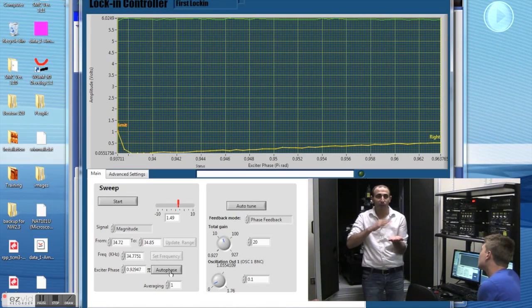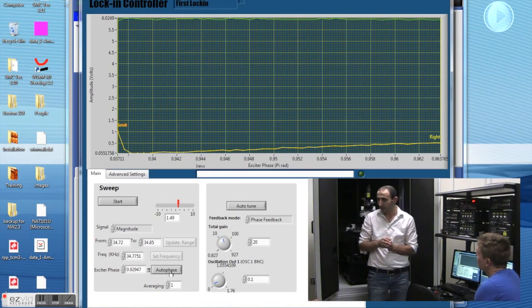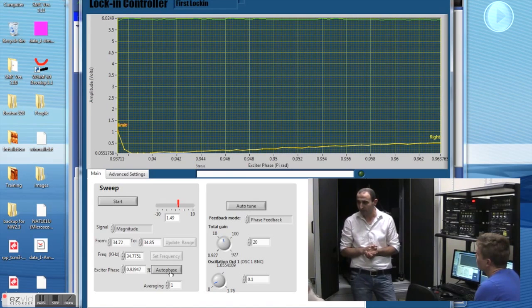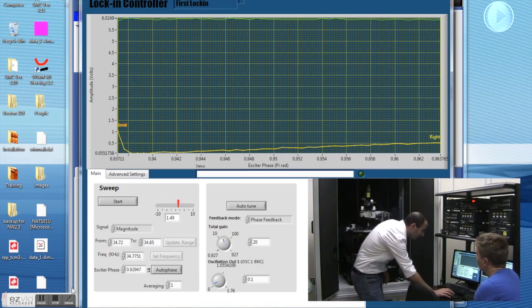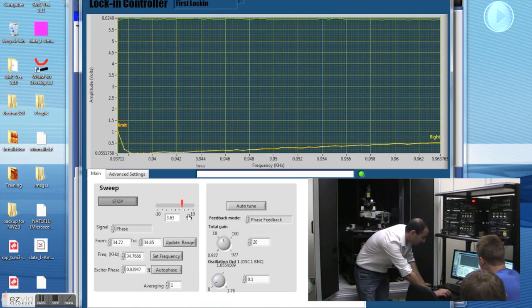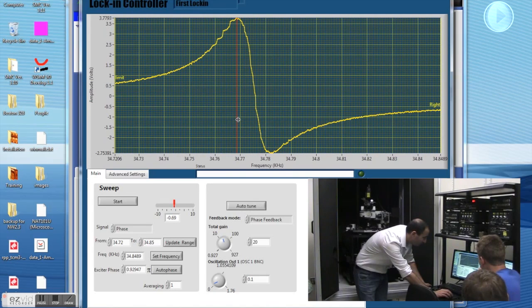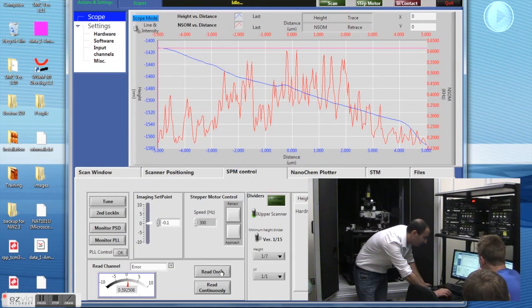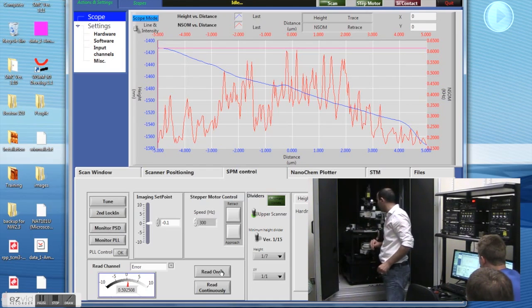So you scan with phase, you get the error signal, you get the height topography information, but the amplitude channel gives you additional information about mechanical properties of the sample. So you don't need to do a force-distance measurement at every point. Here you're monitoring only the amplitude, and it will give you a nice representation of the elasticity, the mechanical properties of the sample. So that's an additional advantage of the tuning fork. Then we shift to phase. Select the zero value here, which is the resonance frequency. And when we're ready to approach, we just put the tip in the correct place above the surface and we'll be ready to go.